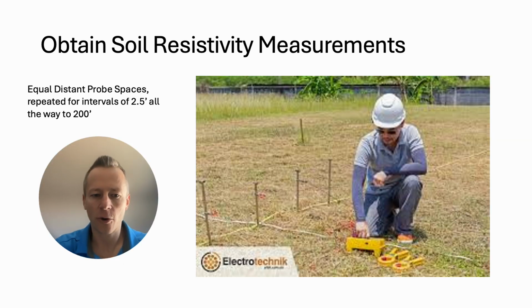As I'd mentioned before, the probes are driven at equidistant spacing. So you can see here someone is out in the field. They've got the little yellow box hooked up to their 4 probes. This is a very close spacing. And then we walk the spacing out. We take one test here and we get one resistance value. And this measures the depth into the earth.